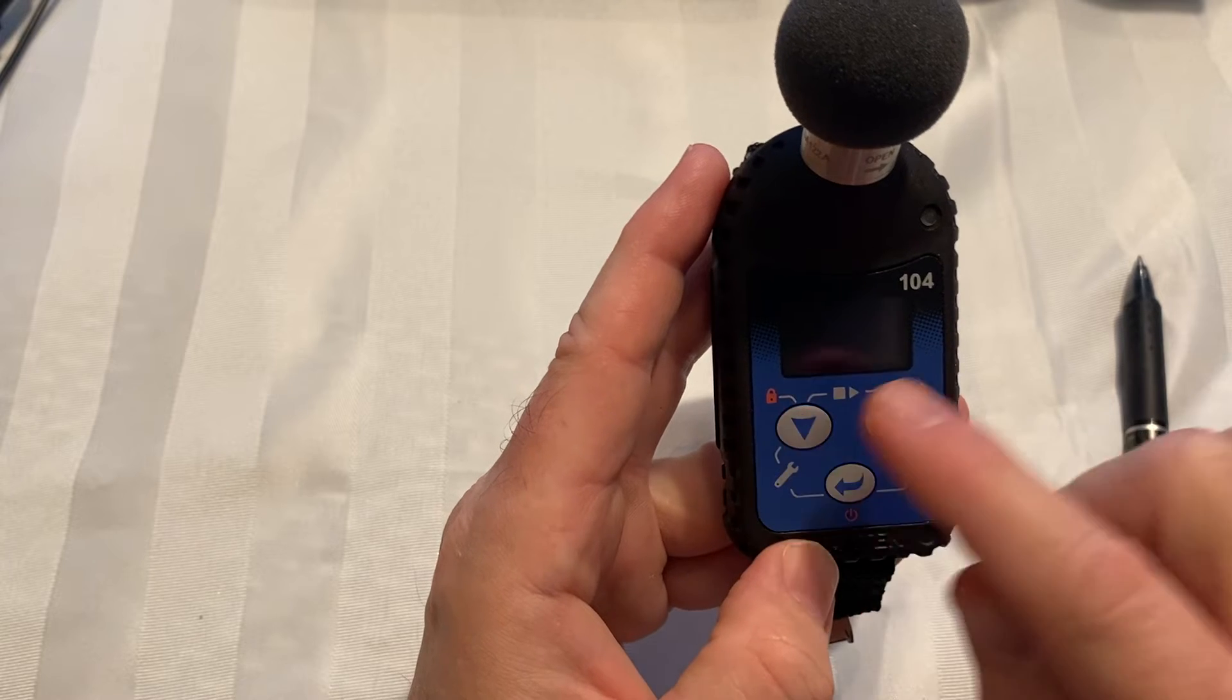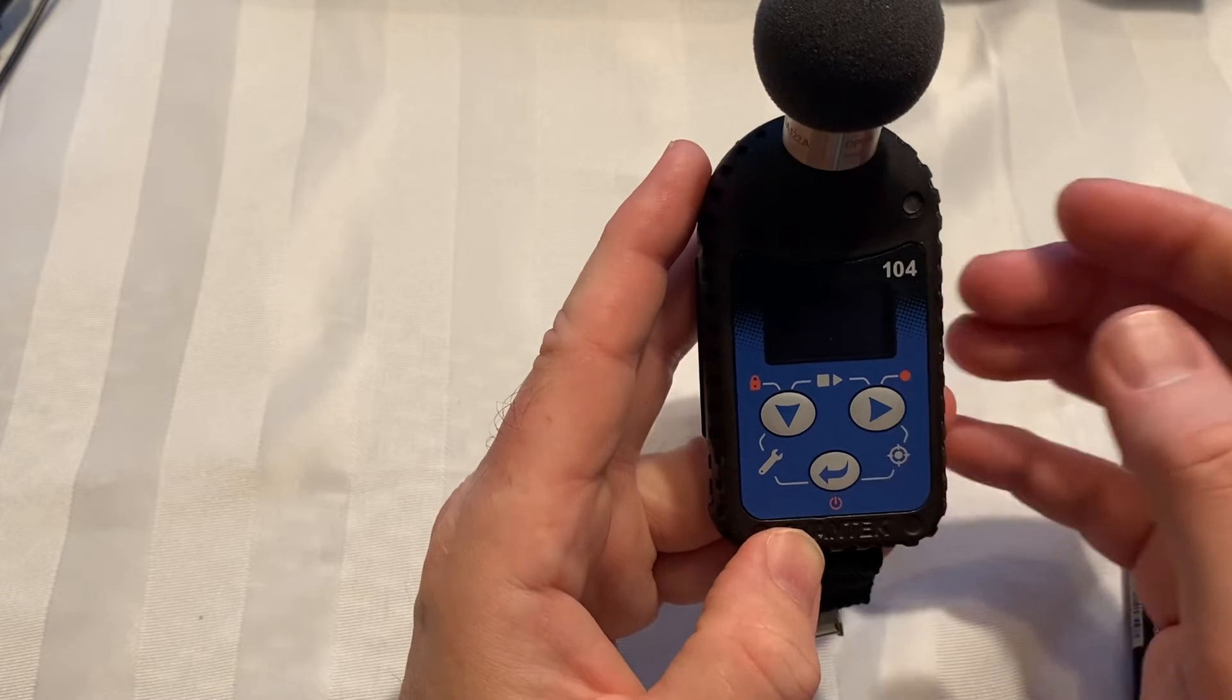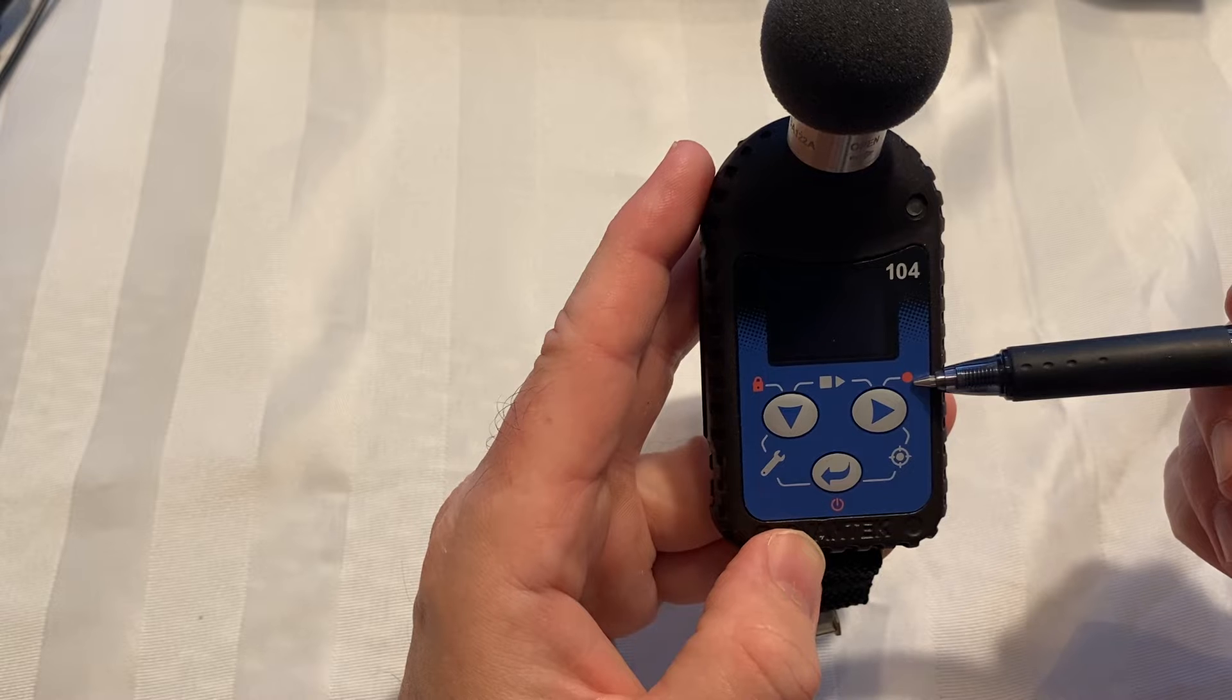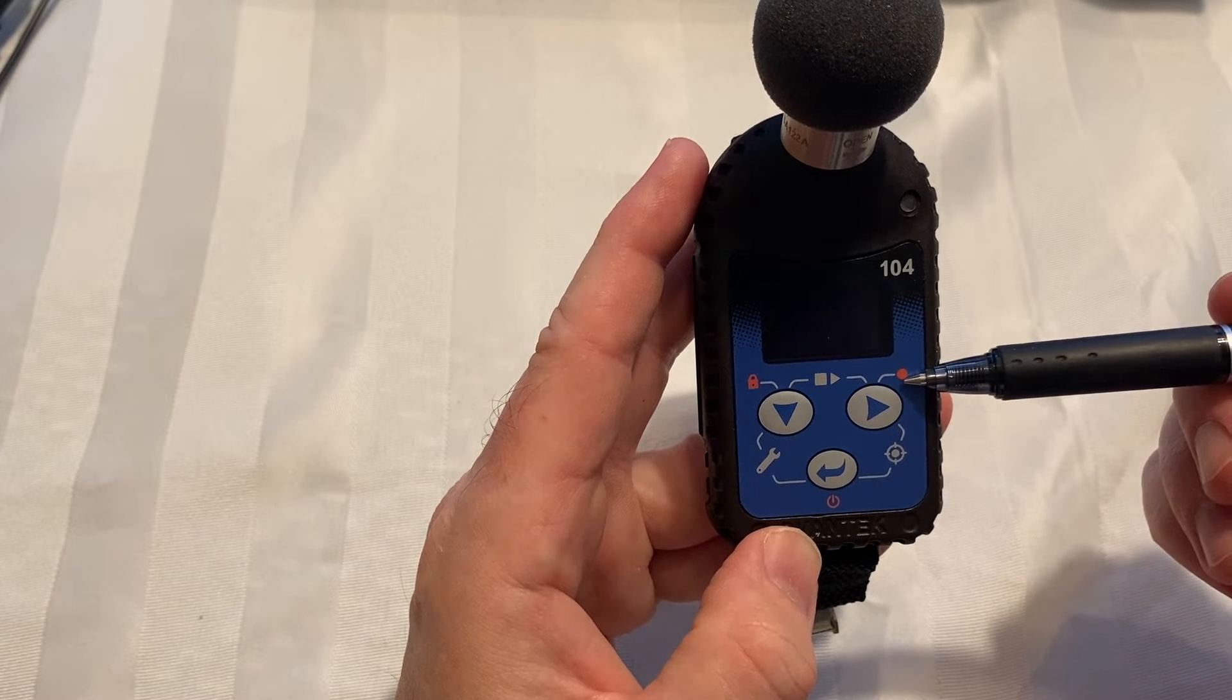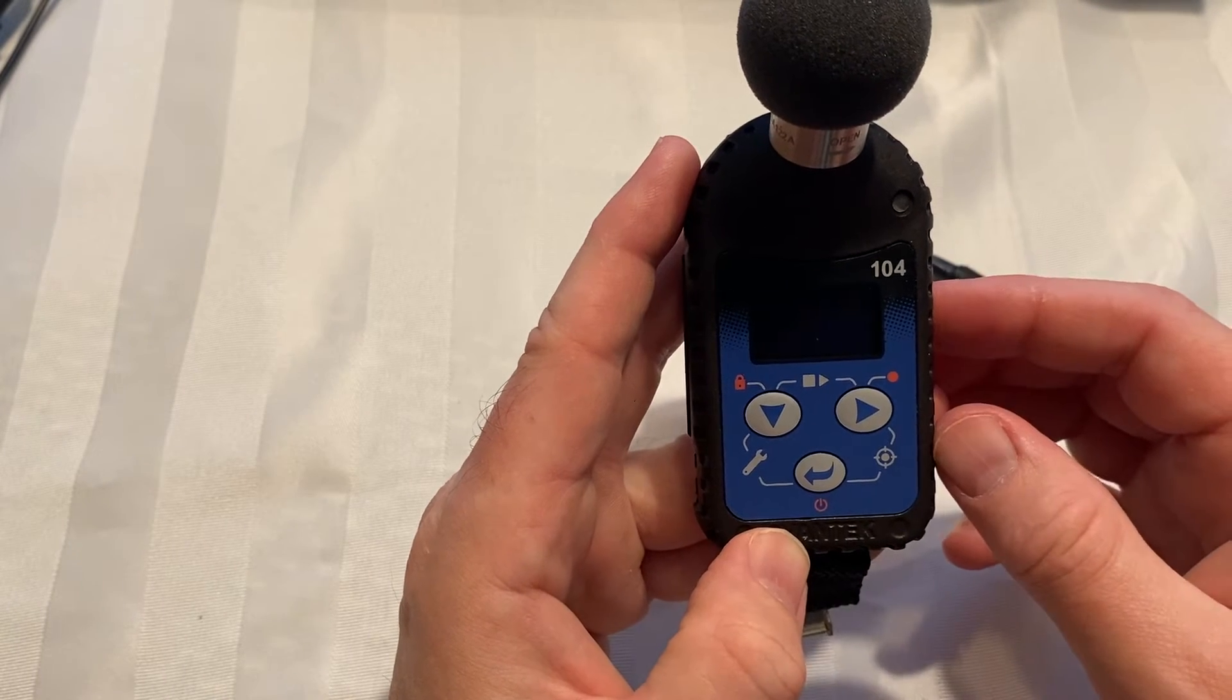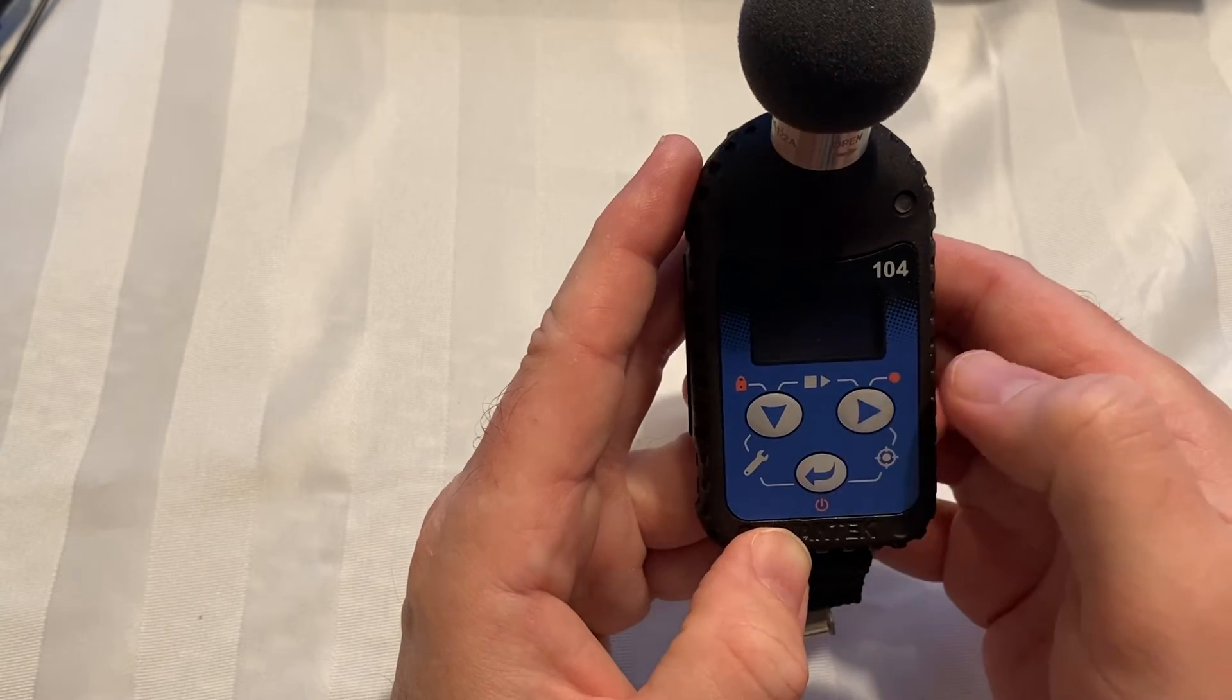The down key and the right key - let's go to the right key next. The secondary option for this key is to record a voice note. So before or after recording, I can make a voice note or voice comment that would give me details on the measurement. That file is stored with the data, so it's a way of making voice notes.